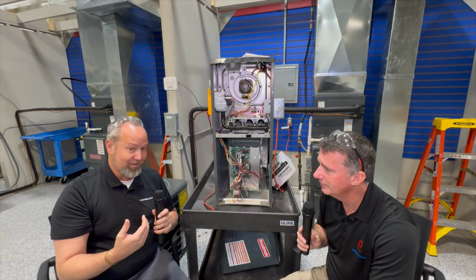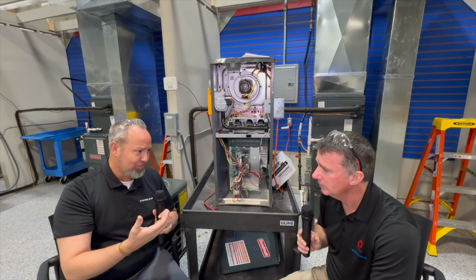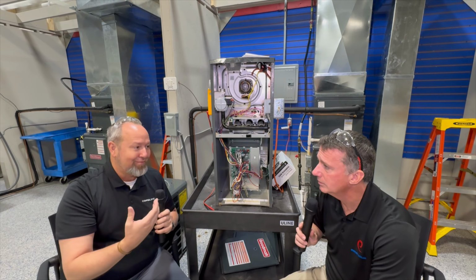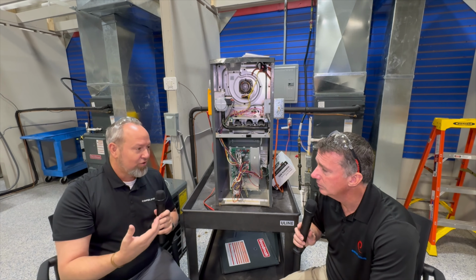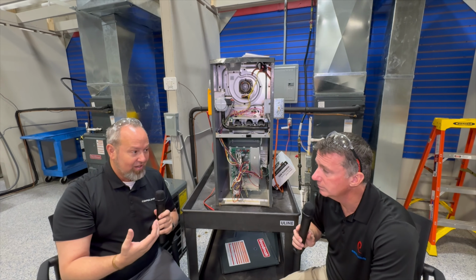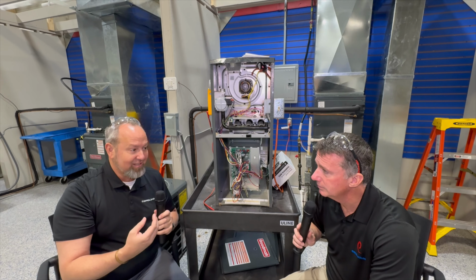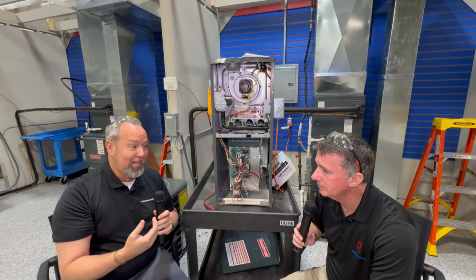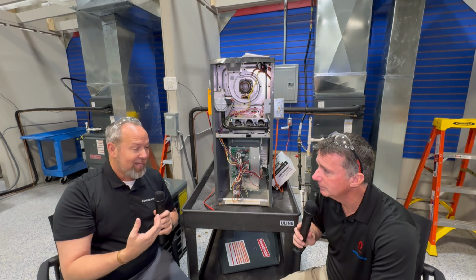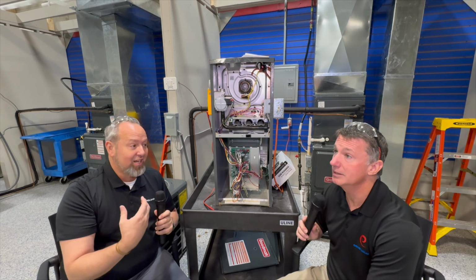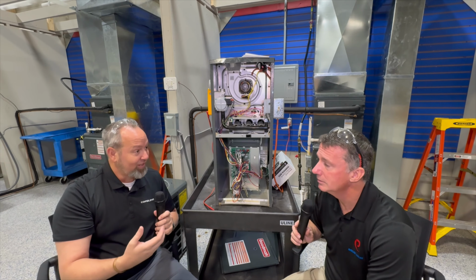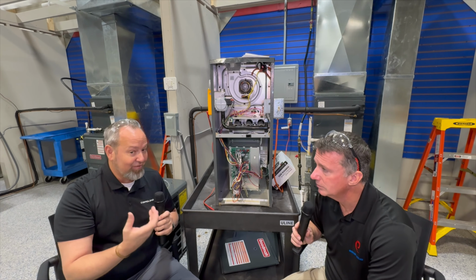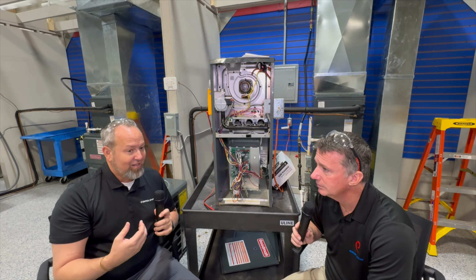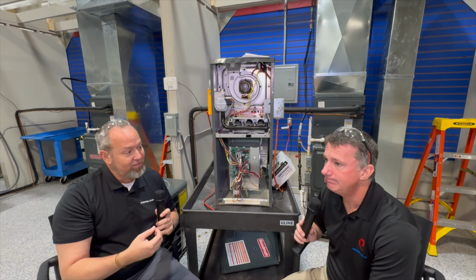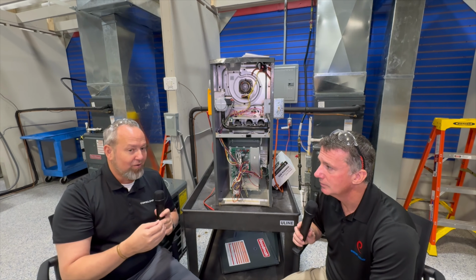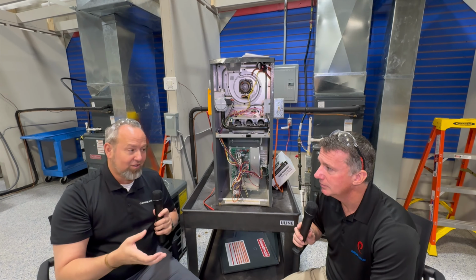It couldn't auto configure, but it doesn't tell you exactly what. You need to say, okay, if I'm getting this error code, which on the 50M56X is an E41, then I need to start looking at what else in this furnace could potentially be the issue, and check that igniter, the inducer motor, the pressure switch, the limit circuit. Make sure everything's good, because for the auto harness configuration to configure properly, the rest of the components have to be functioning the way they should.